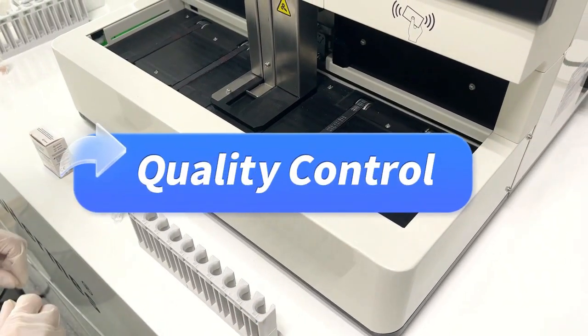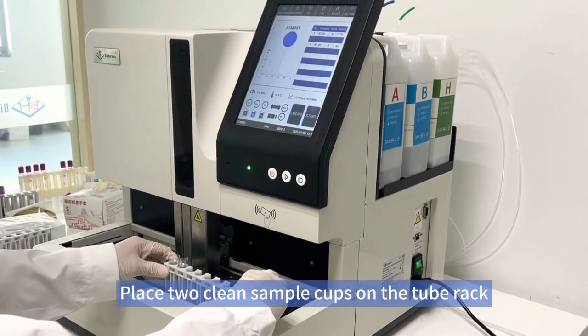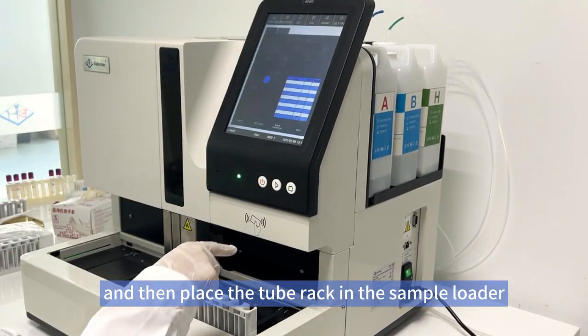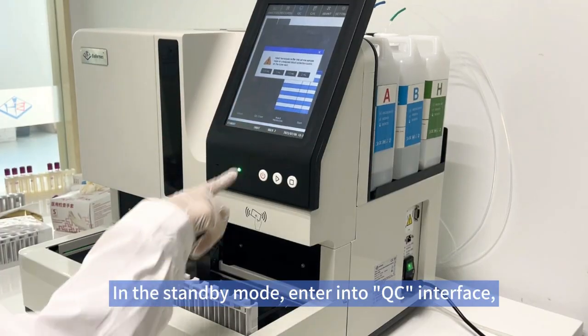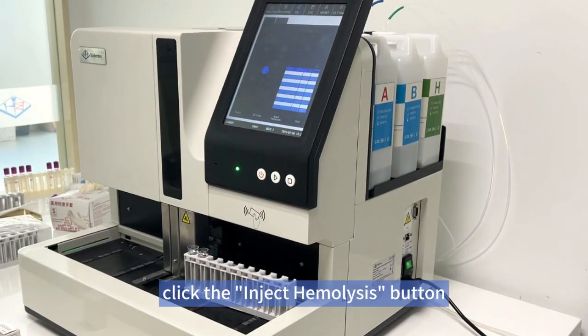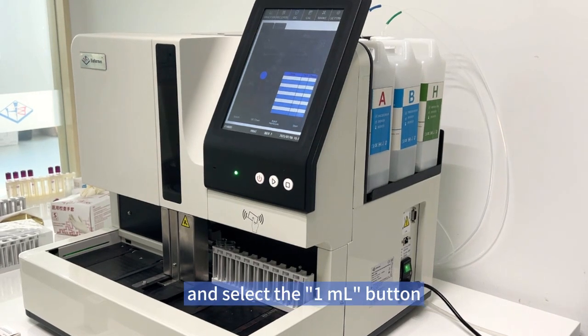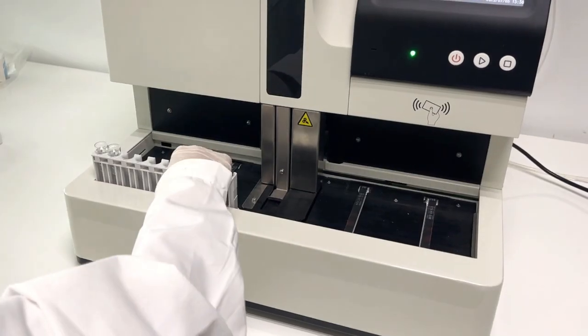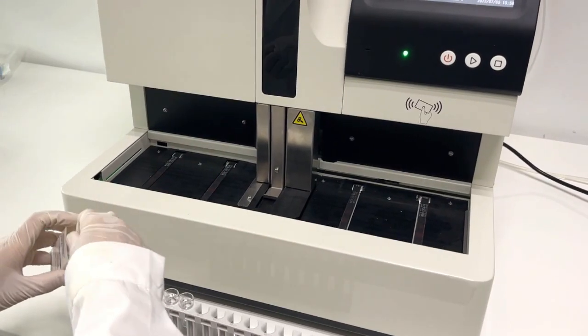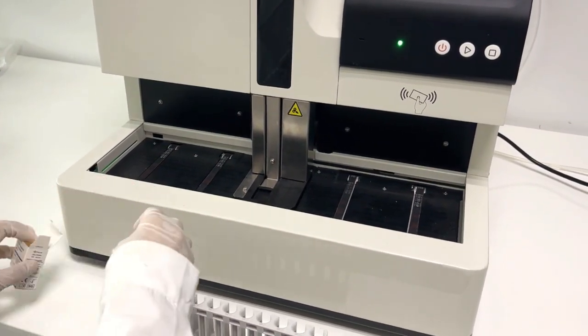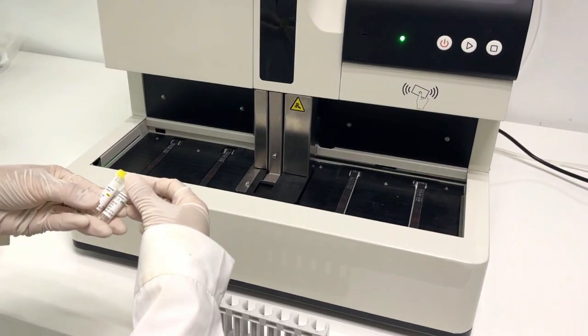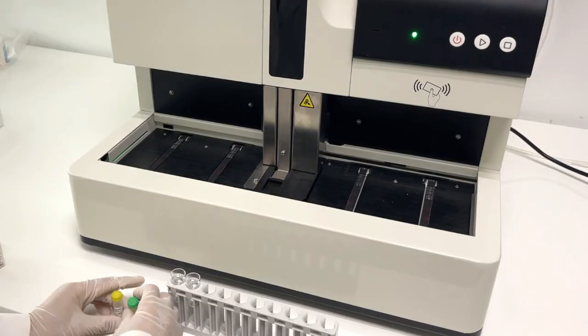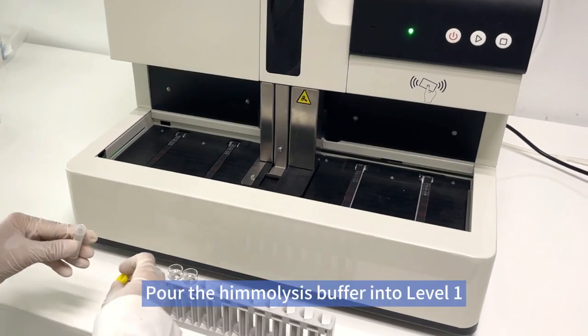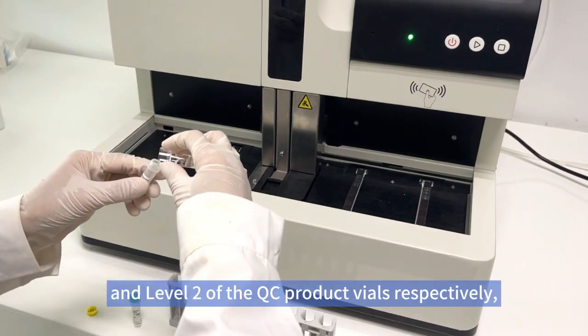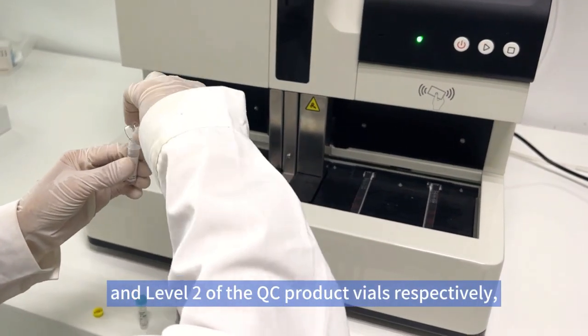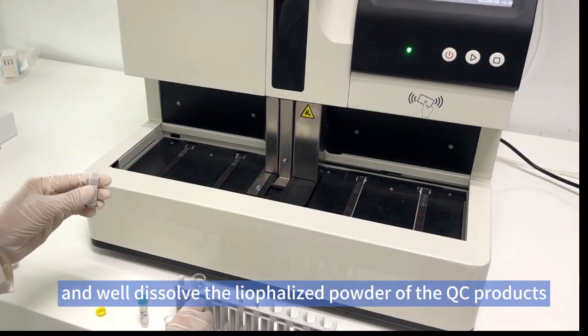Quality control. Place 2 clean sample cups on the tube rack, and then place the tube rack in the sample loader. In the standby mode, enter into QC interface, click the Inject Hemolysis button and select the 1 ml button. Pour the hemolysis buffer into level 1 and level 2 of the QC product vials respectively, and well dissolve the lyophilized powder of the QC products.